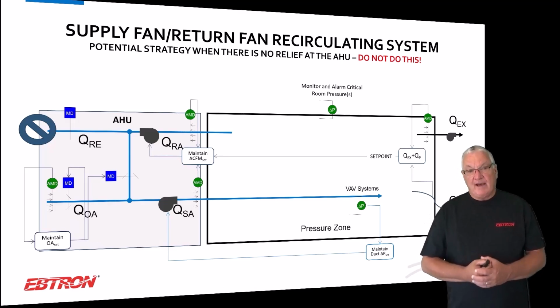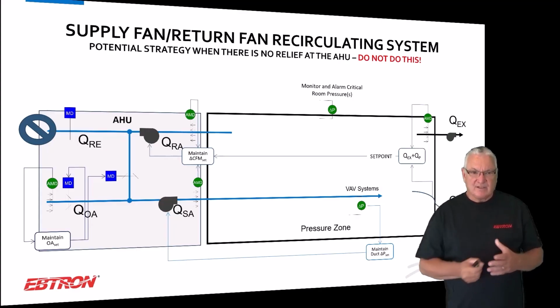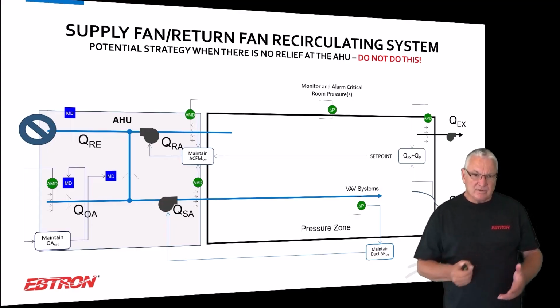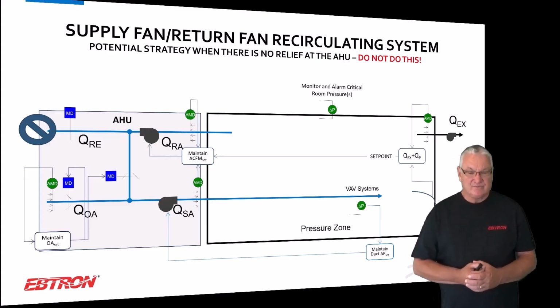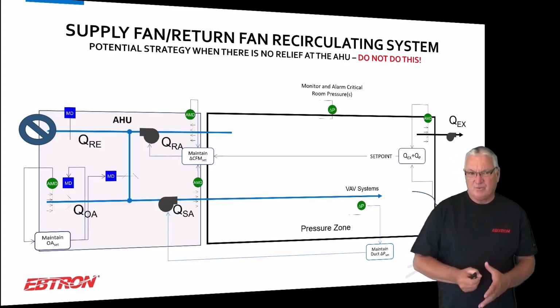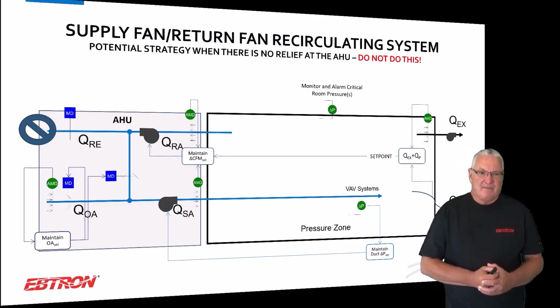Now, what we have seen people do, and this is a do not do: they say, we're all in on this flow control stuff. We're going to measure supply, return, and outdoor airflow rates. We're going to modulate our intake and recirc air dampers, maybe one or both, however you decided to do it. There's a better way, and I'm going to show you some good ways, but at any rate, I'm going to do that to maintain my outside air.